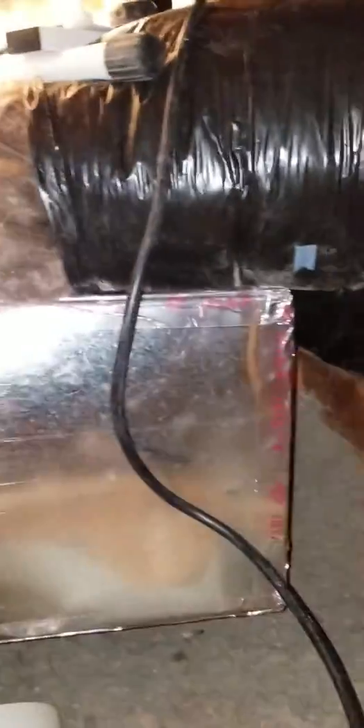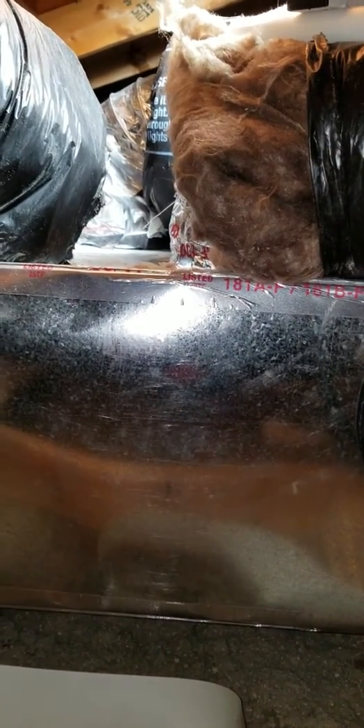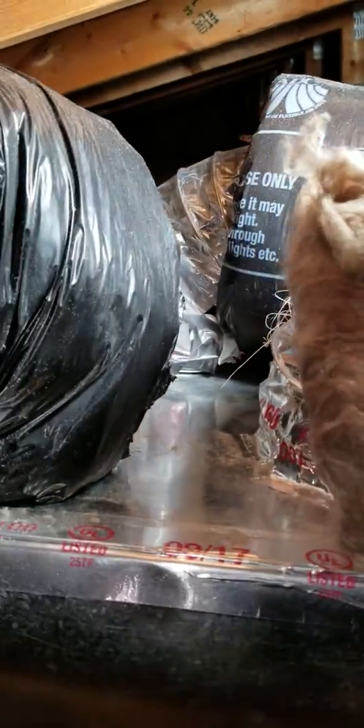You can see what the heating contractor has done here — basically just ran some ductwork through the attic, running these ducts all the way around up here. This right here is a giant trunk where the heat comes in from the furnace and then gets redistributed out to the other rooms in the house. It's actually getting distributed into the attic up on top, where all the individual room trunks come out — and it's not sealed up very well.